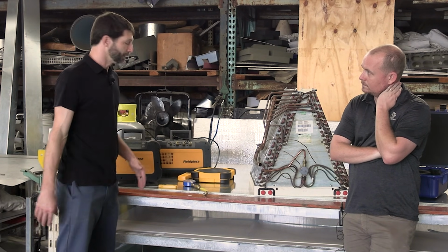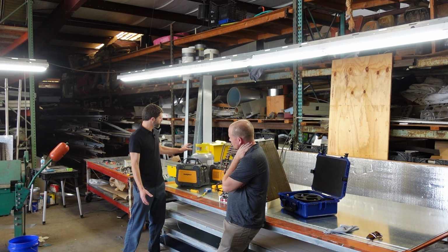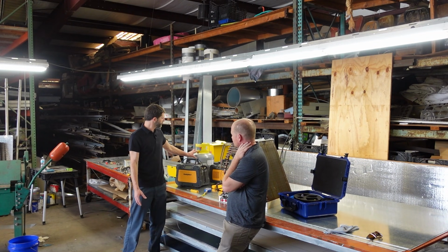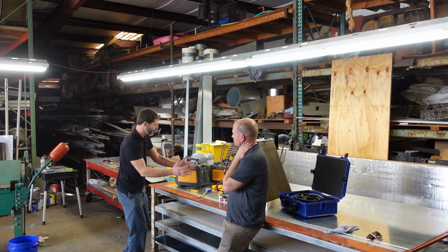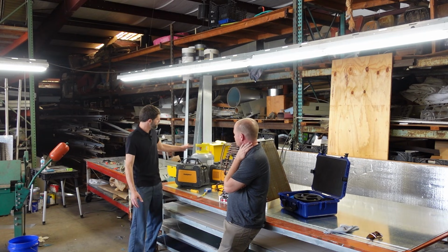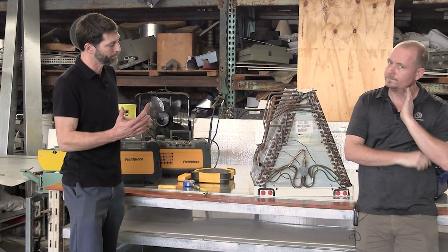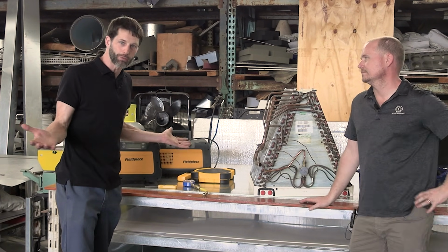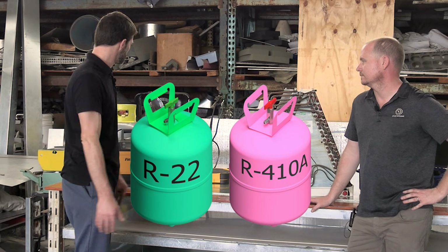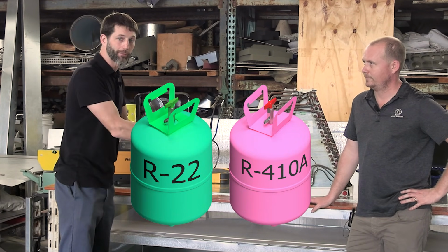Now, via the EPA standards, we're not supposed to really be charging units with refrigerant from a recovery bottle if we're pulling it out of multiple systems. If we pull refrigerant out of a system, we could potentially reuse it, but it's always best to use new refrigerant, just to make sure that you're not recontaminating the system that you're working in.